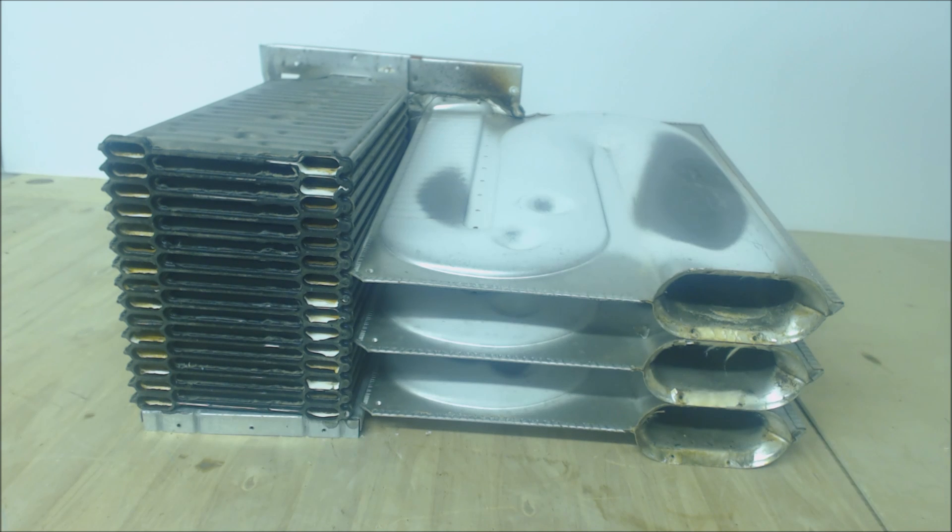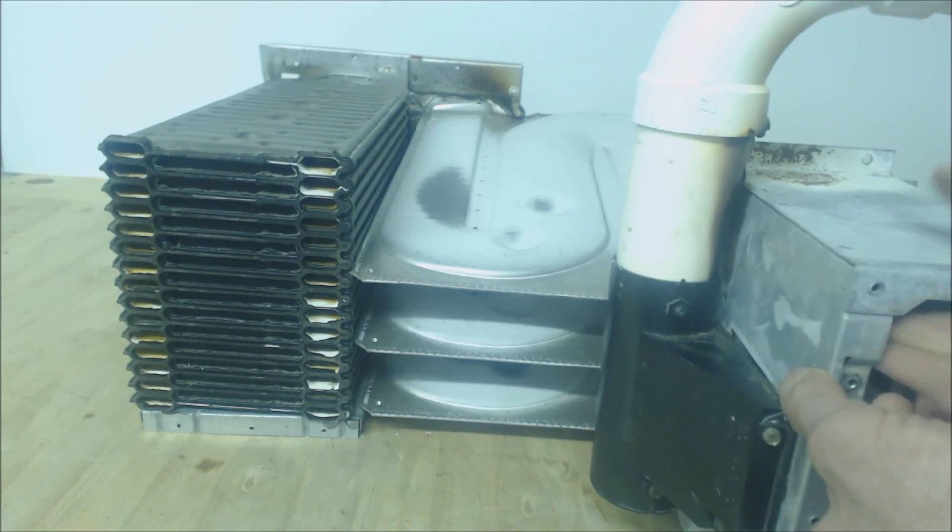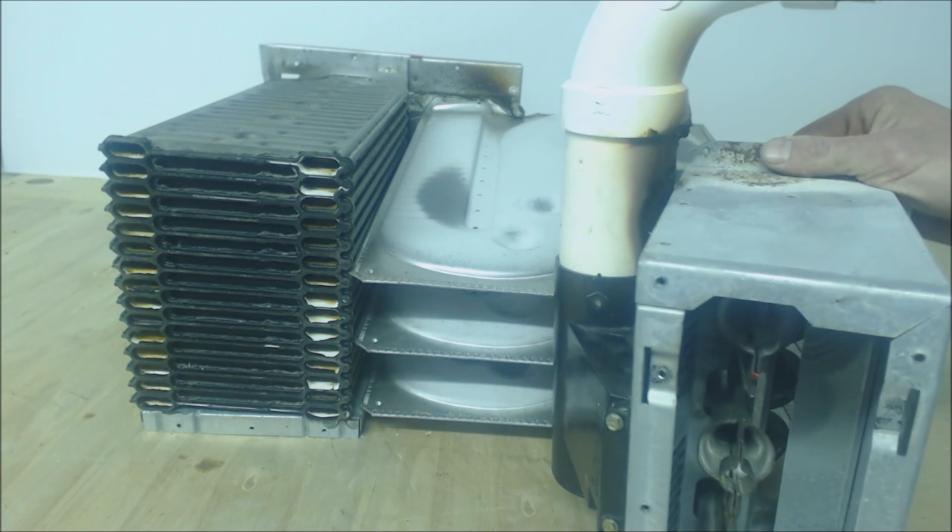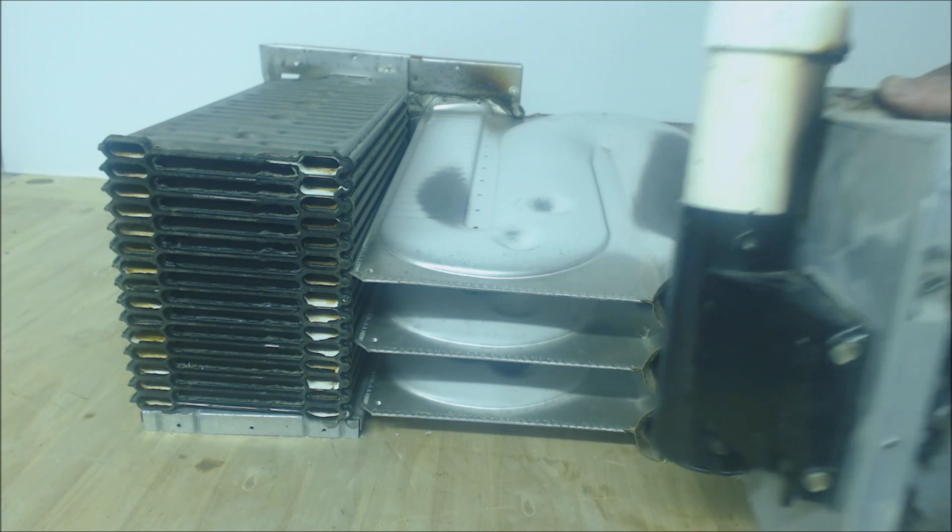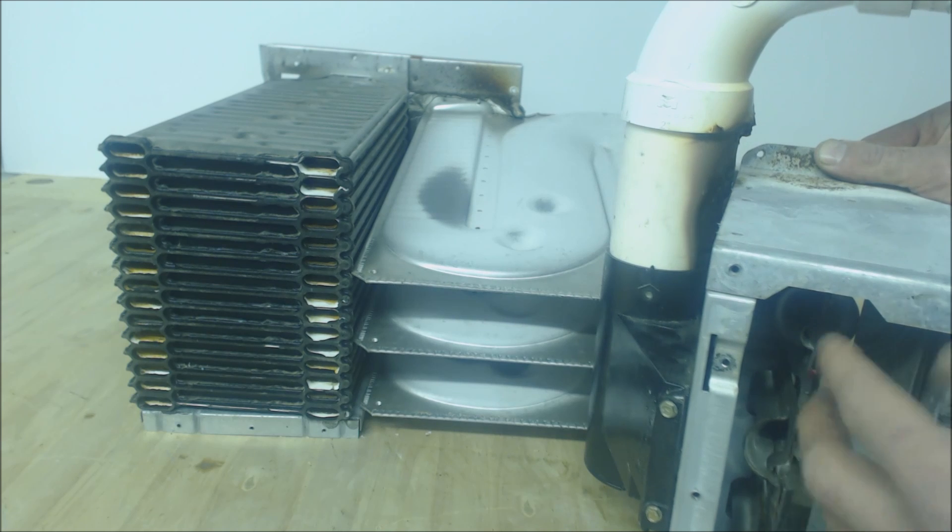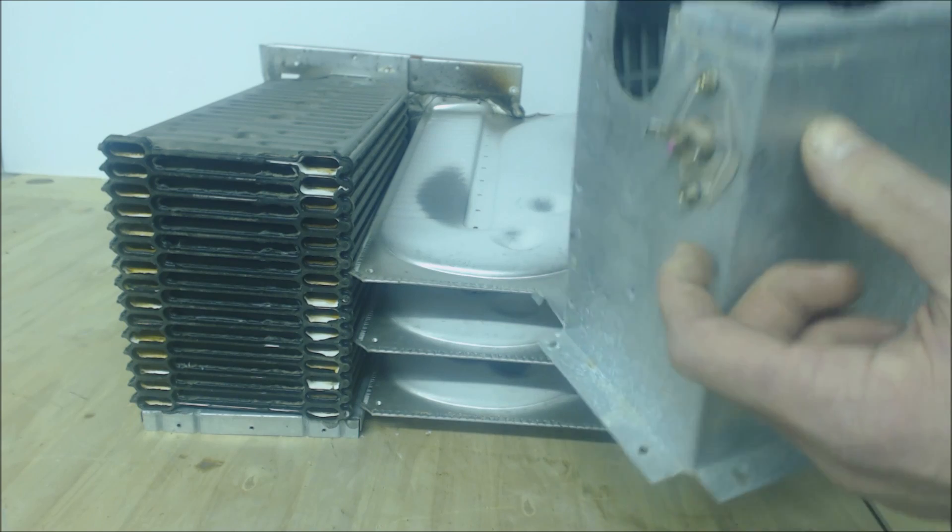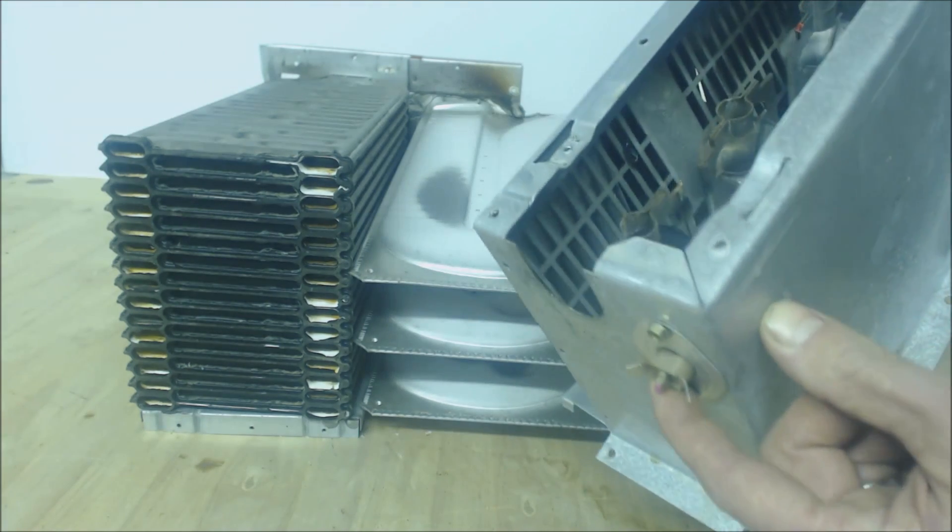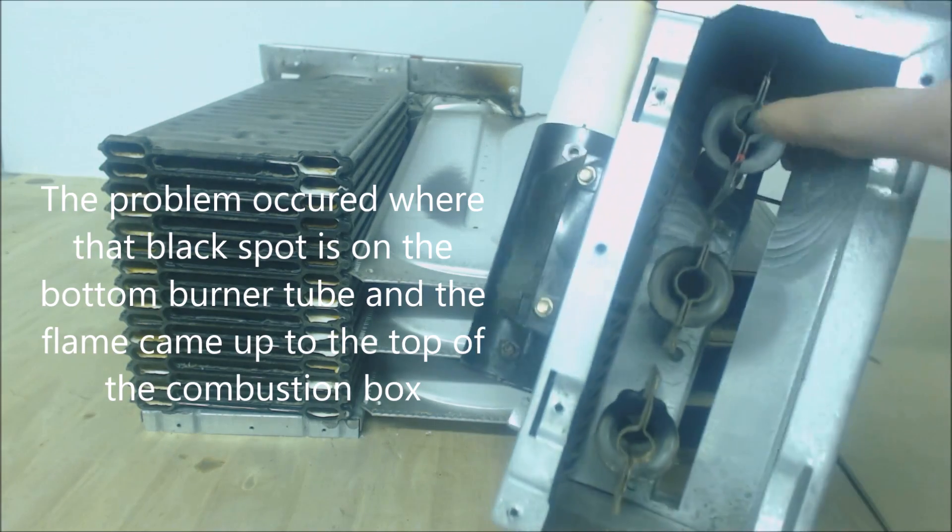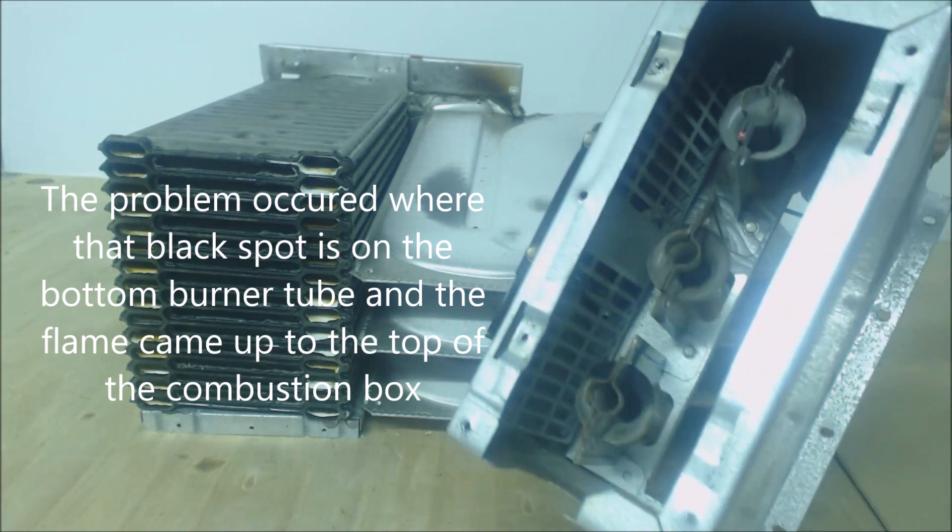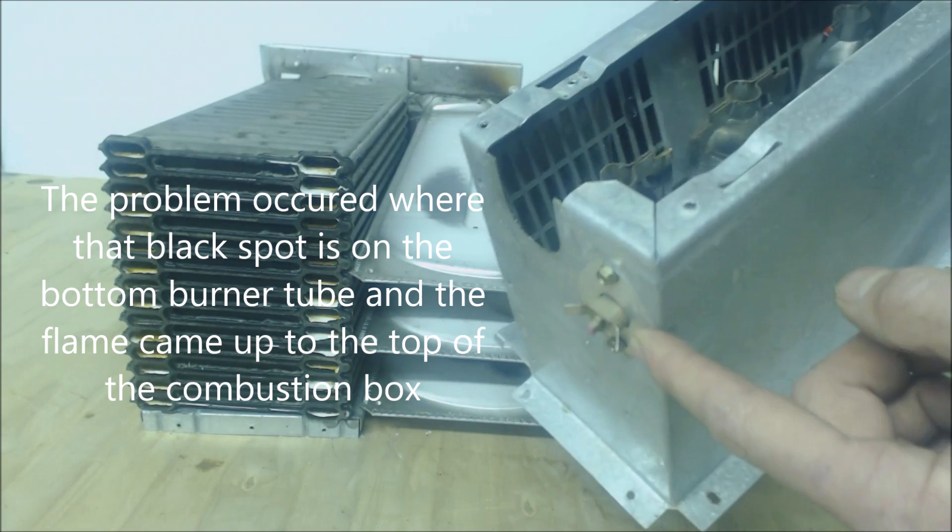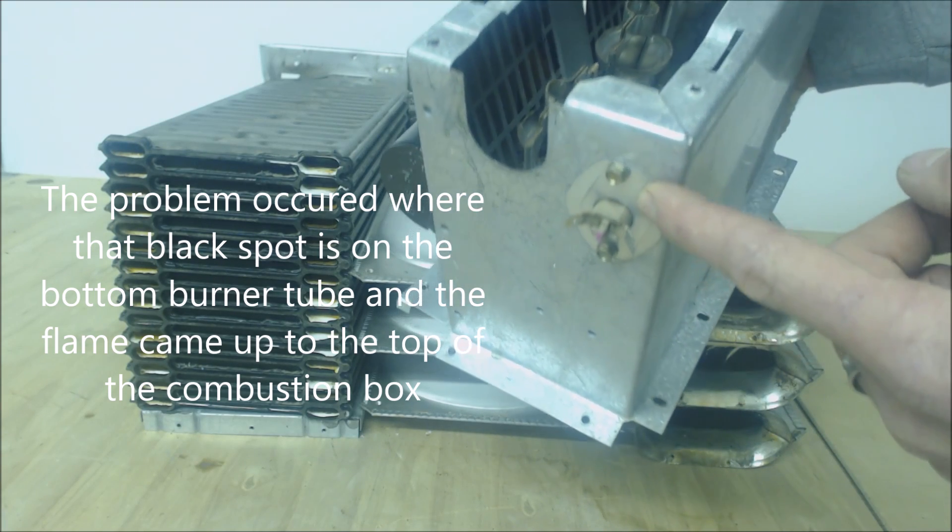Here is the combustion chamber right here. It connects right onto here. You have your one, two, three burner assemblies right there, and on this side you have your flame rollout switch. You can see the problem occurred over on this side. There was no flame rollout switch over here, and that's why you see a lot of combustion areas now have two, sometimes even three flame rollout sensors.